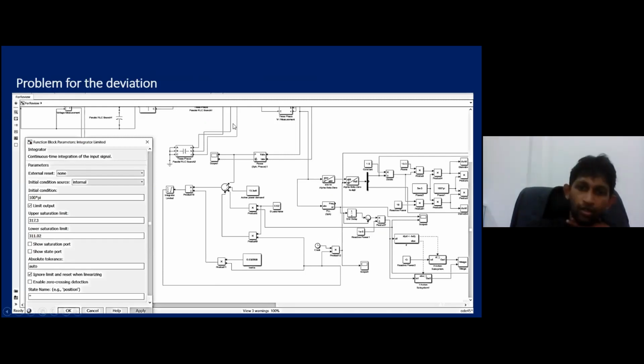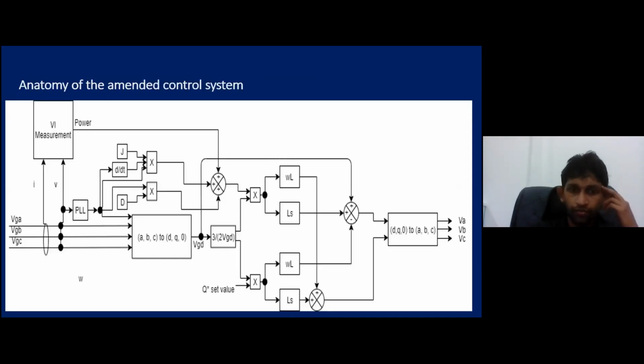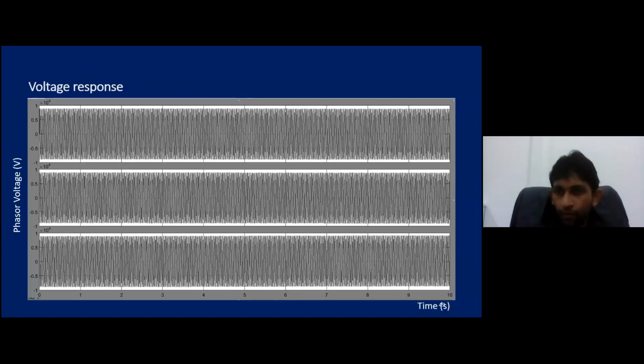The problem was this: we had an upper saturation limit and a lower saturation limit, 50.5 or 49.5. So we changed the approach by not directly setting the frequency, but setting up the power deficit by adding the acceleration power to the system. The results were promising; we got a good result.